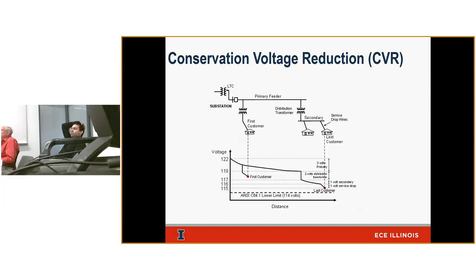That leaves a little bit of drop for the primary before you start getting into the violation range. So we're talking about maybe 6 to 7 voltage points or volts that you can drop across the system before seeing any violations.